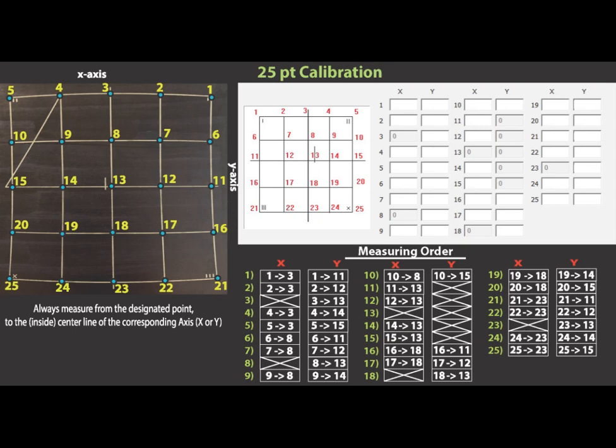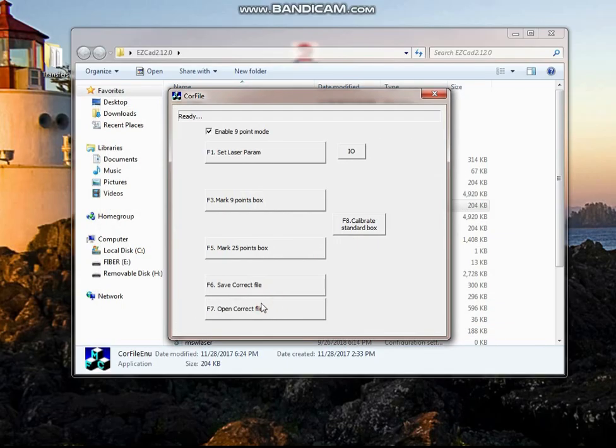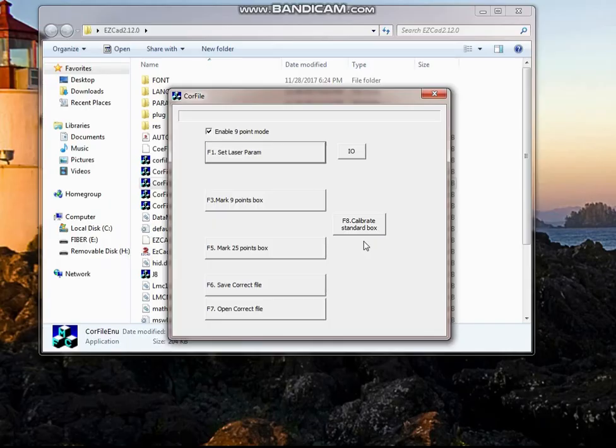that we're adding to our calibration. So this is the 25-point calibration diagram. You want to make sure that you're following the measuring order just like you did in the 9-point, and using the same level of precision you did as well. Be sure to take your time because this part of the calibration is the most important. And once we finish that, we'll hit OK.